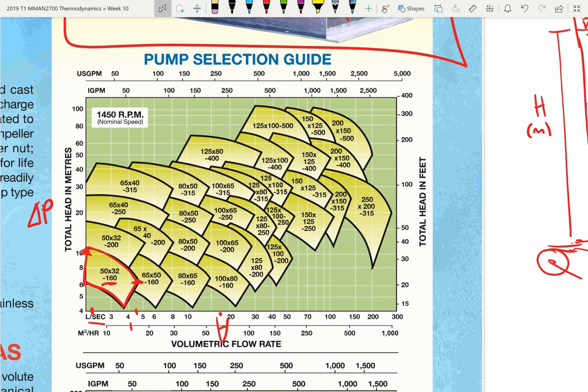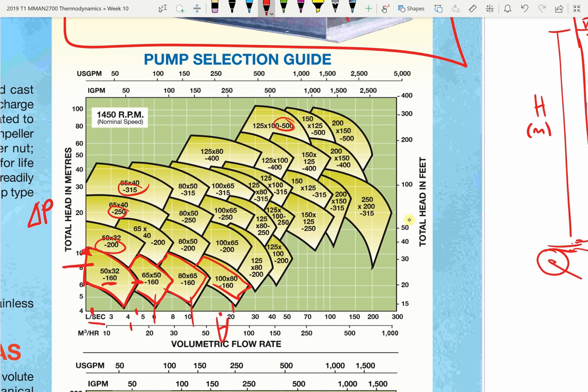Pumps with larger inlets and outlets produce a similar total head in metres — a similar pressure — but greater flows, as we go to the right-hand side of the chart. Pumps with larger impeller diameters — 200mm, 250mm, 315mm, 500mm — produce more ΔP. So to go up this graph, it's not enough to just have larger inlets and outlets; you also have to have a larger impeller.